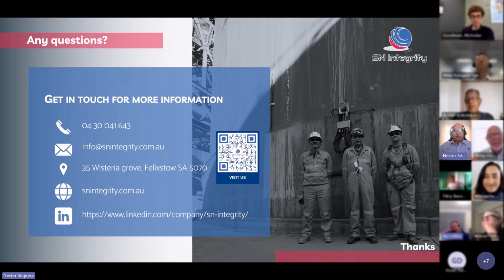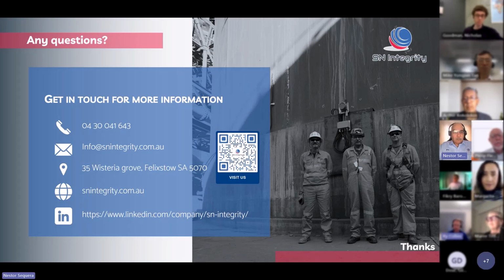Yeah, thanks, Nestor. It's really good. I'm familiar with the system. I just wonder, for this particular vessel, is it running at elevated temperature? I believe it's running at 140 at the bottom, but up there it's about 70 degrees C or something. And your equipment and the cabling are spec'd to operate at elevated temperatures. I suspect they put some insulation and cladding back over your sensors on the vessel.